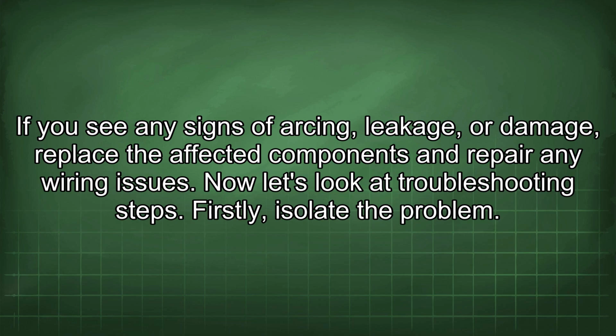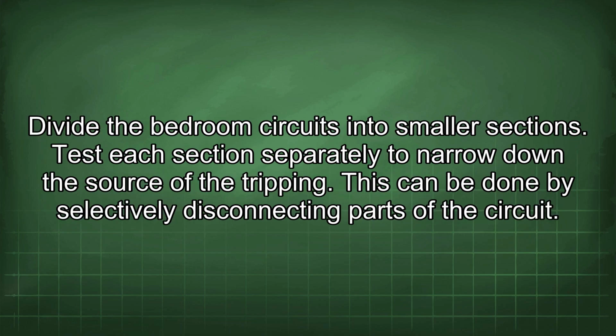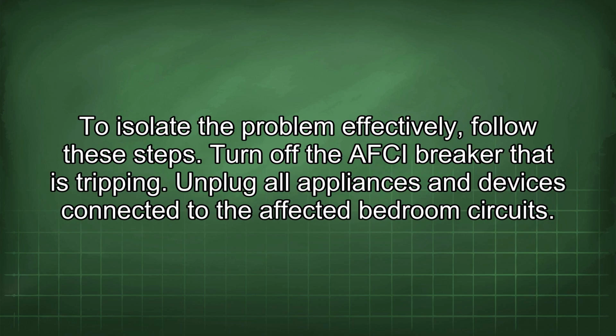Now let's look at troubleshooting steps. Firstly, isolate the problem. Divide the bedroom circuits into smaller sections. Test each section separately to narrow down the source of the tripping. This can be done by selectively disconnecting parts of the circuit. To isolate the problem effectively, follow these steps.